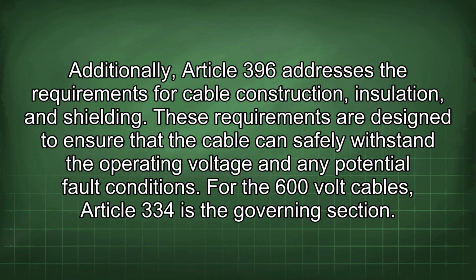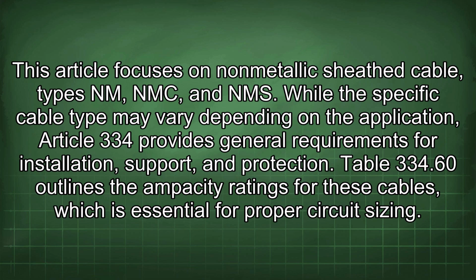Additionally, Article 396 addresses the requirements for cable construction, insulation, and shielding. These requirements are designed to ensure that the cable can safely withstand the operating voltage and any potential fault conditions. For the 600-volt cables, Article 334 is the governing section. This article focuses on non-metallic sheath cable types NM, NMC, and NMS. While the specific cable type may vary depending on the application, Article 334 provides general requirements for installation, support, and protection. Table 334.60 outlines the ampacity ratings for these cables, which is essential for proper circuit sizing.